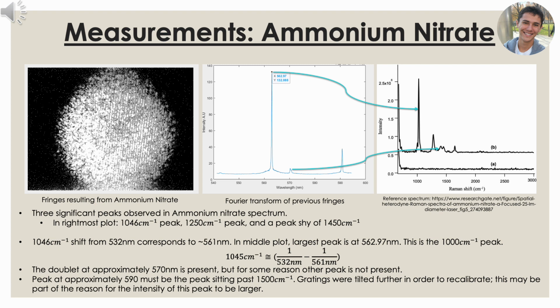Now, if you look at the right side, sitting at around 590 nanometers, we believe that this might correspond to the 1500, 1600 inverse centimeter peak, as seen in the reference spectrum on the right. We're not entirely sure why this peak is larger than the doublet sitting in the middle, but it should be noted again that these gratings were tilted in order to recalibrate our system. So this might be partially why the intensity of this peak is larger, but for the most part, we believe that we at least have the positions of the wavelengths properly set.